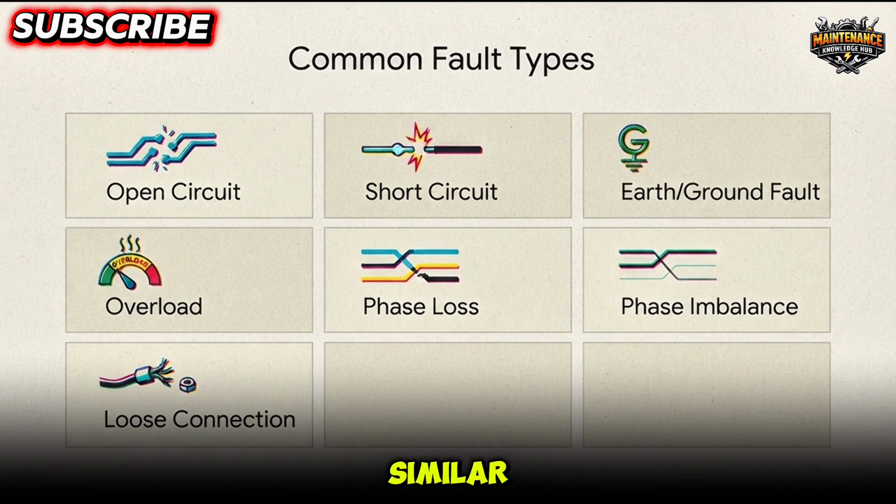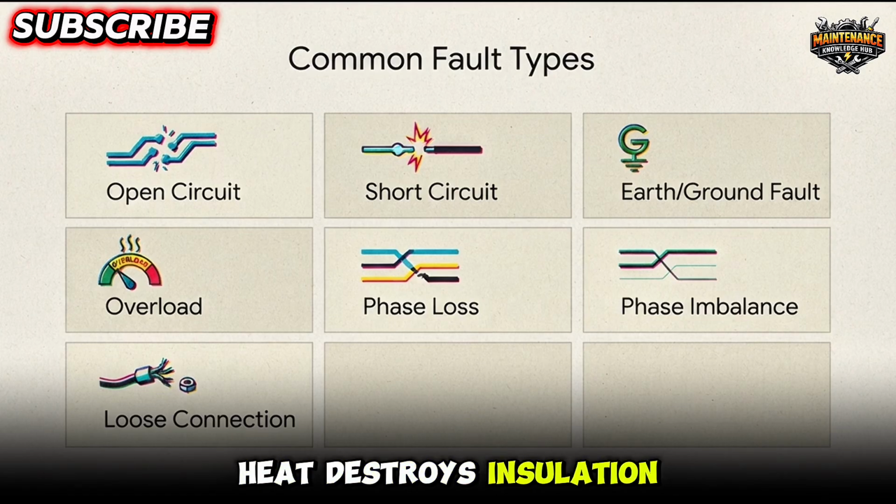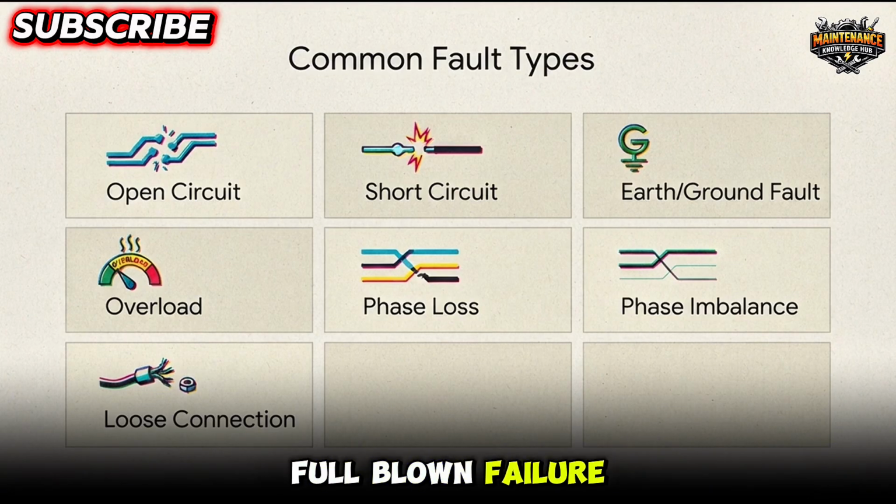Phase imbalance is kind of similar. It's this insidious issue that just slowly cooks your motors over time. Finally, never ever underestimate a simple loose connection. It is the silent killer. Loose connections create resistance, which creates heat, which destroys insulation, and boom, you've got a full-blown failure.